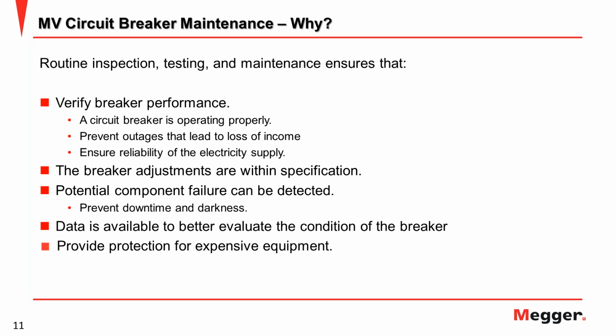Okay, now why do we need to do maintenance on the medium voltage circuit breaker? The circuit breaker is intended to switch on and off electric current on the distribution network for routine operation and protection of other equipment. So electric transmission system failure and equipment destruction can occur if the circuit breaker fails to operate because of lack of preventive maintenance. So if you don't do good maintenance, maybe you will find some issue like this.